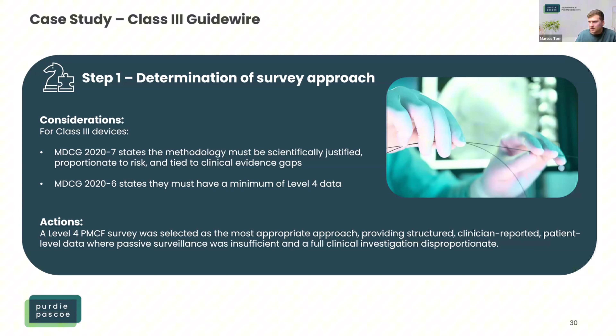We need to then design a robust survey protocol and questionnaire. Looking at that guidance again, and ISO 14155, you must have a formal protocol, pre-specify things as objectives, endpoints, and then eligibility criteria, sample size justification, and methodology. So we designed a thorough survey protocol, listed out a safety and performance endpoints and the associated acceptance criteria that had been determined through a literature review of the DUE and the SOTA. The performance endpoint was deemed as procedural success, so successful advancements of the guide wire to the target location, an acceptance criteria of greater than 90%, and we were looking at freedom of adverse events with an acceptance criteria of less than or equal to 4%.